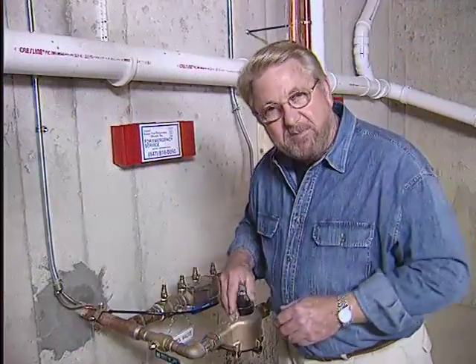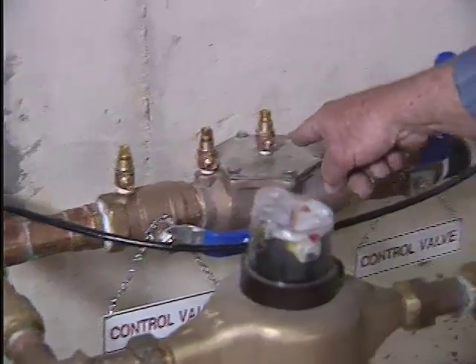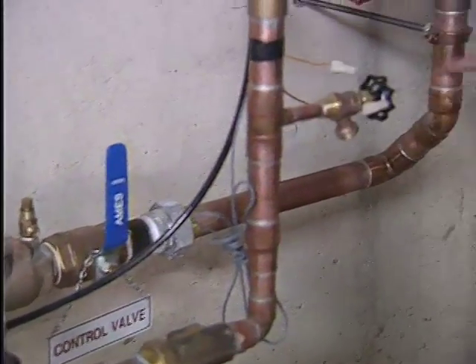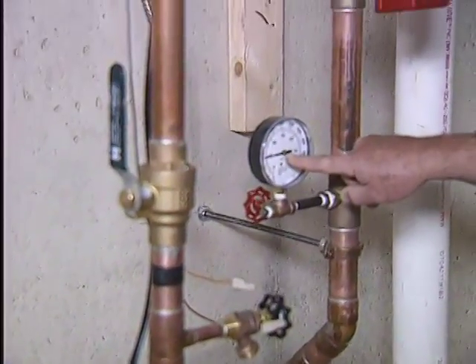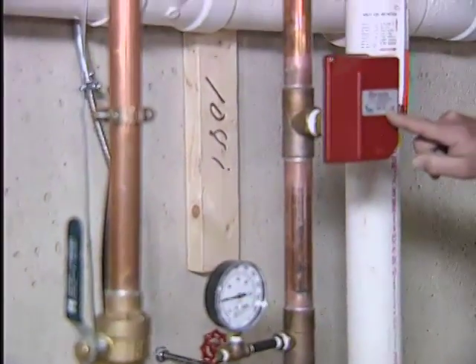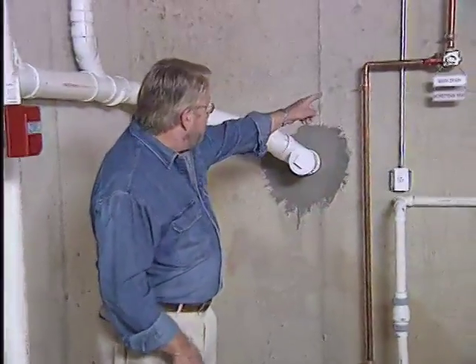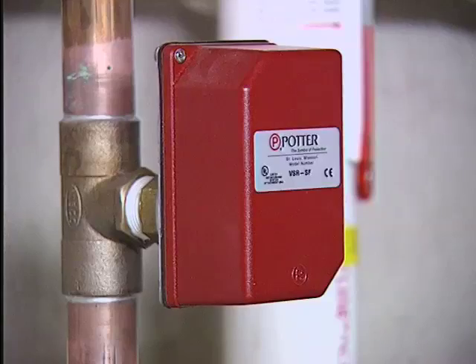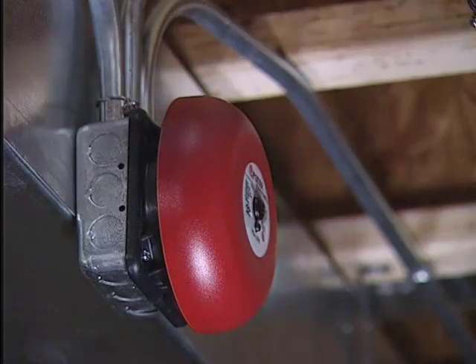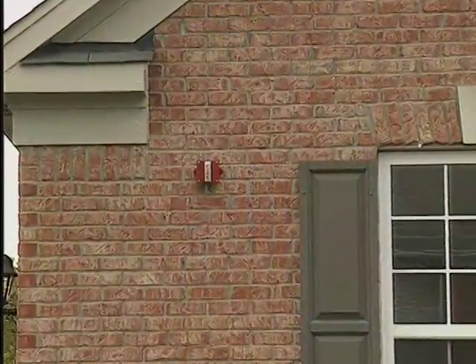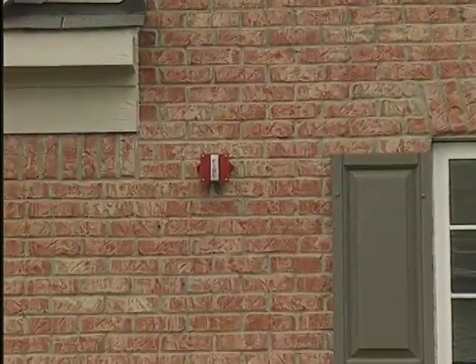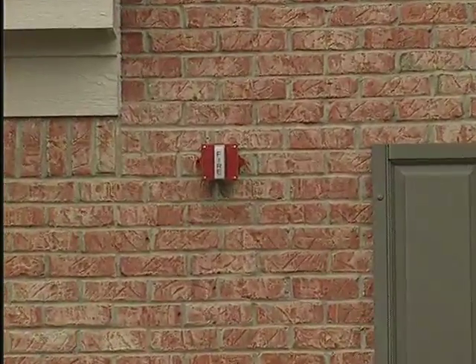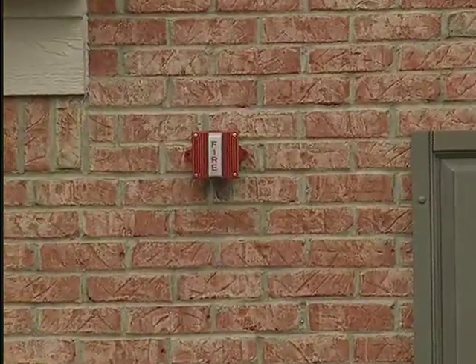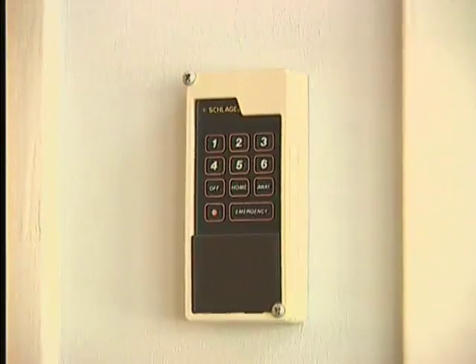The fire sprinkler system attaches to the main water supply right here at this T. Then it passes through a backflow valve, up into this riser, through a pressure gauge, finally through a flow switch and alarm. Now, over here is the drain and test assembly. The flow switch detects any water flow through the system and is wired to an inside alarm bell. The flow switch can also be wired to an outside horn or strobe to alert neighbors to sprinkler activation in case fire strikes when no one is at home, or to a monitored security system.